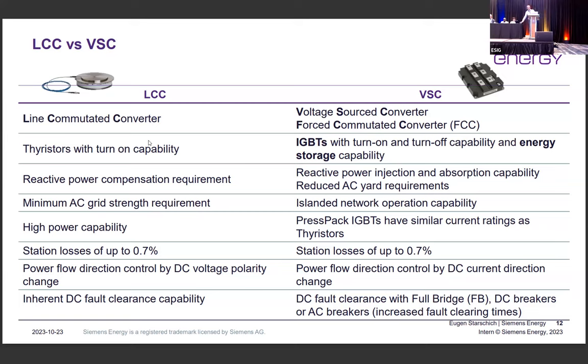And this is a kind of tool for building up the network. And there was the question: how are we going to go multi-terminal with the LCC if we want to change the power flow direction? We are transmitting from station one to station B and we want to change the direction of power flow. What we need to do in the LCC is to change the DC voltage polarity, which for point-to-point is straightforward. It's not an issue. As soon as you're building up multi-terminal and you want flexibility in the power flow direction, this becomes a problem. And this is where the VSC technology has the big advantage, because it does not change the DC voltage polarity, but changes the DC current direction.